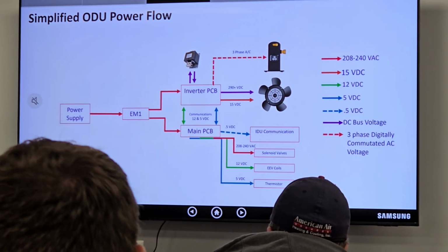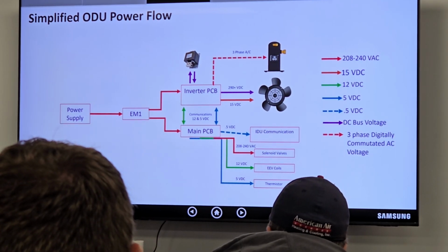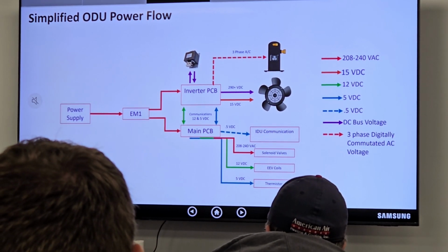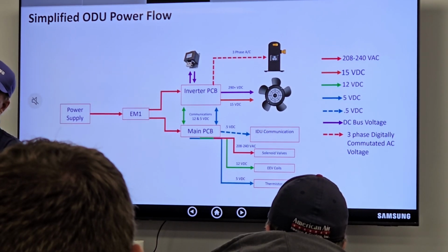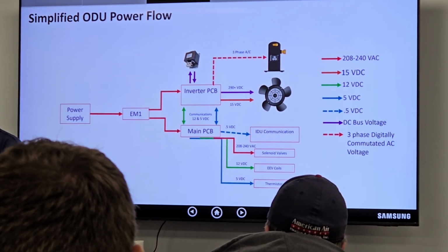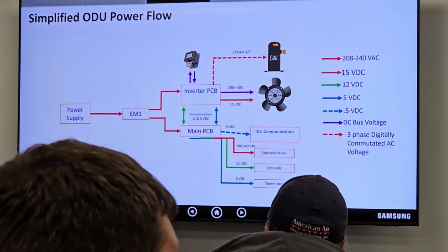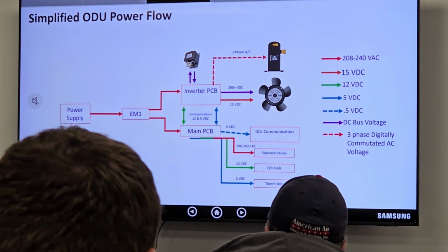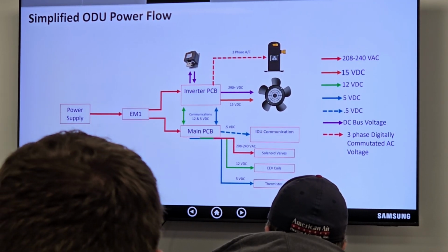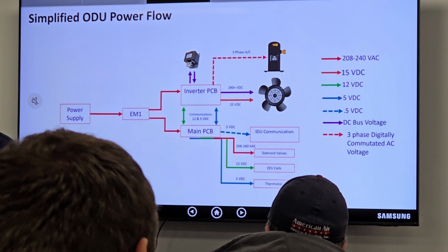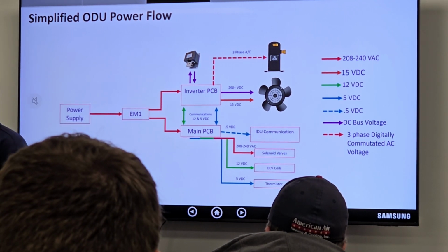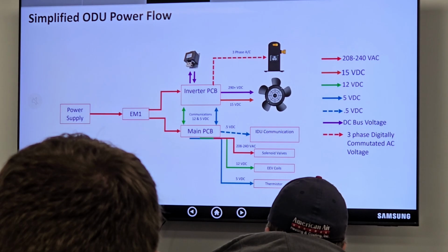So whenever we ask, communication problems usually is this wire here, does not have a crimp terminal on the end of it, and we're not using a ring terminal to stick up underneath the terminal so we get good connection. Now I've had units been in the field for 4 or 5 years. Communication error code, I ask them about the wire and the landing. Do you know what the response is I get? It's been working all along.